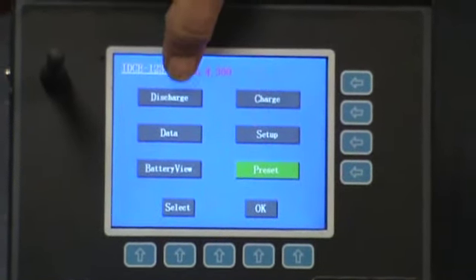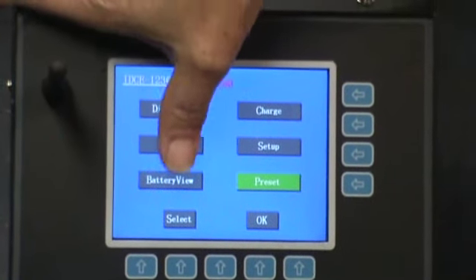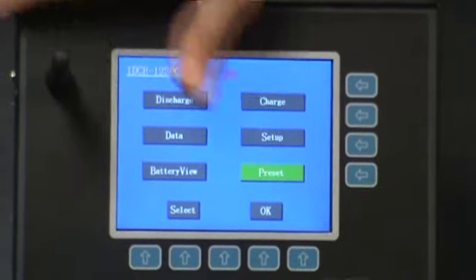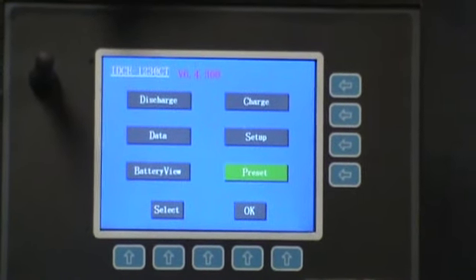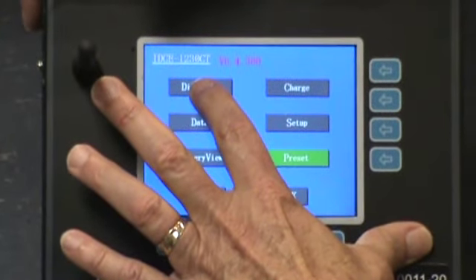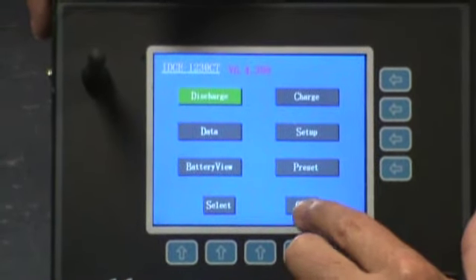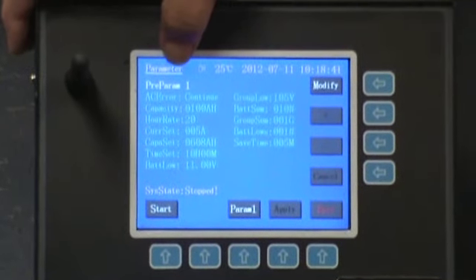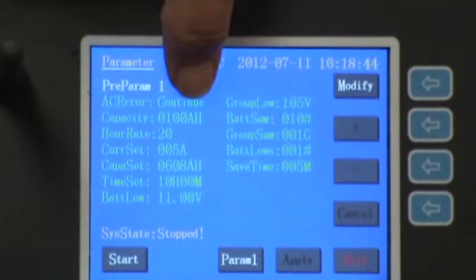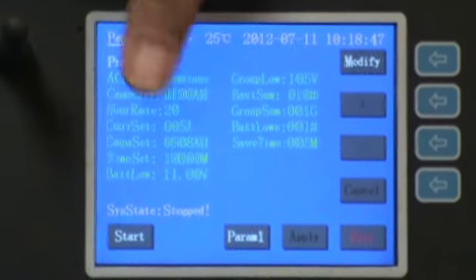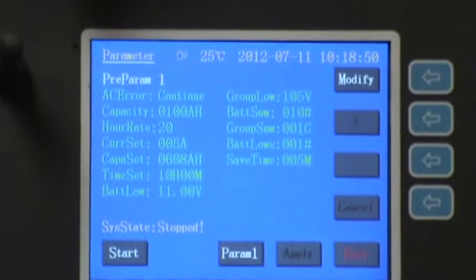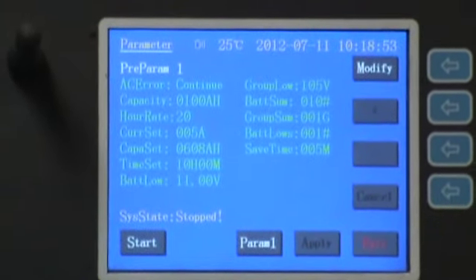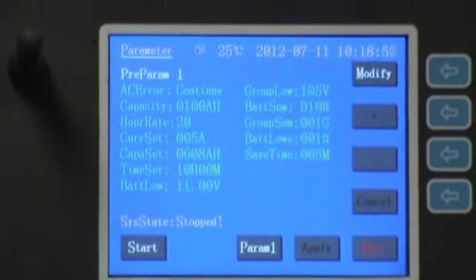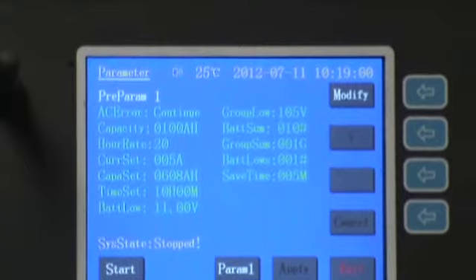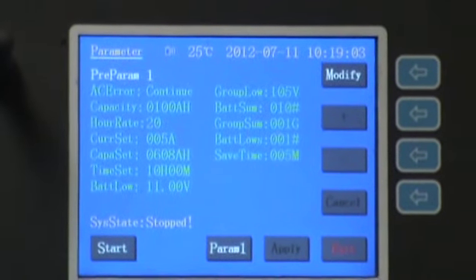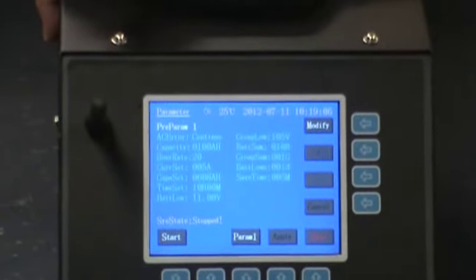Now your possibilities on the screen give you discharge, data, battery view, charge, setup, or preset. We've done the preset, and I've got it set so that we can do a discharge. So we go into the discharge and say OK. It now tells me what my parameters are set for: 100 amp hours, the hour rate is 20, and I'm only going to do it at 5 amps. This baby is capable of going all the way up to 300 amps. It'll do anything from 48 volts all the way up to about 300 volts. So you have an extreme range of voltages and an extreme range of currents it'll handle.